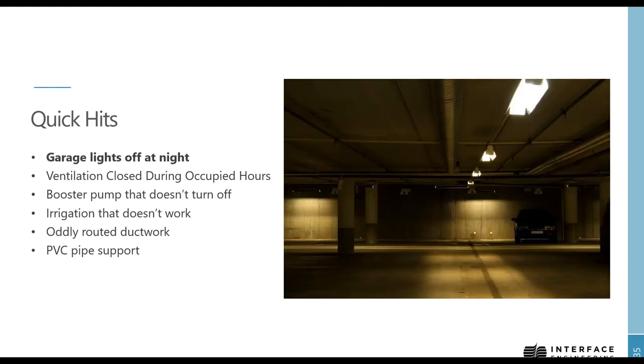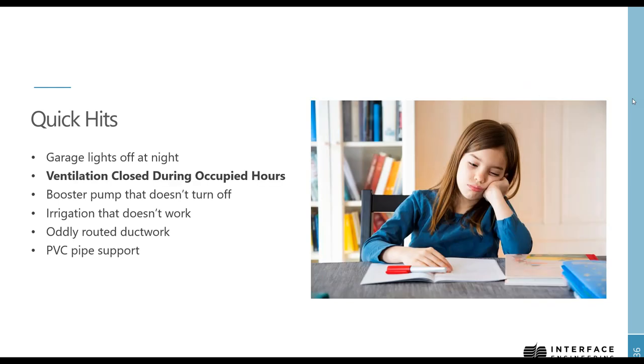So the first one here is garage lighting controls. Them being off at night. So it's great for energy savings, but not for occupant safety. The system is tested by the contractor during the day, but then when we come in for testing, we find that the time schedule is incorrect, or the photo sensor is located near another light. These are all quick fixes, but certainly not something you want to deal with once the building is already occupied.